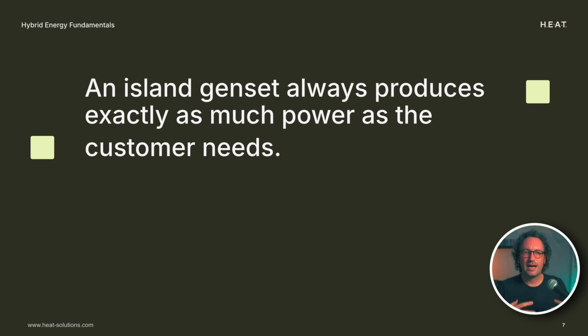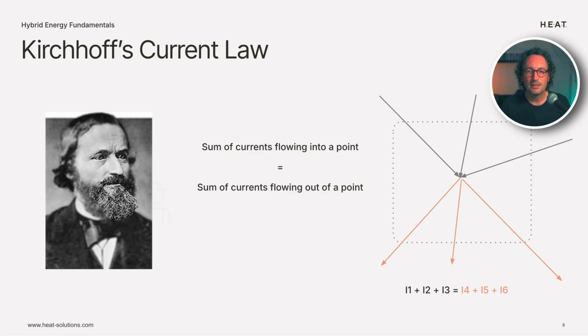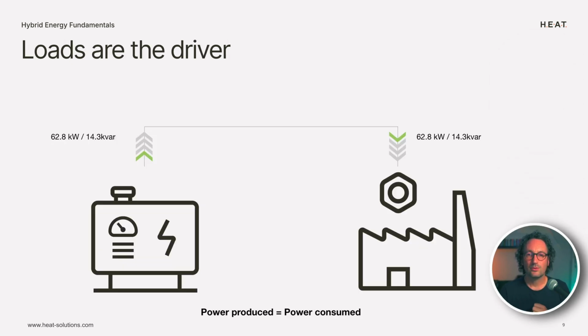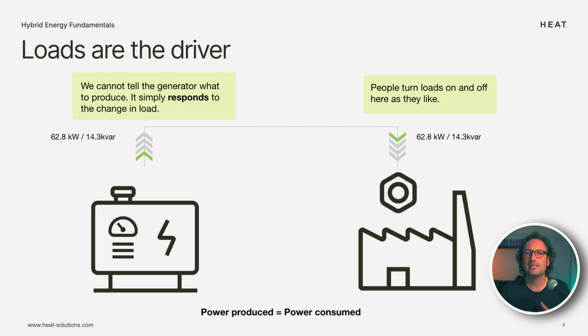Okay, so we know that an island genset is always producing exactly as much power as the customer needs. But the big question is, how does it know? And for that, I'm going to refer to Kirchhoff's current law. Kirchhoff's current law states that the sum of currents flowing into a point is always exactly equal to the sum of currents flowing out of a point. And the key thing here is that this is always true whether you like it or not. It's a physical reality of the world that we live in. Nobody's got to make it happen. It just is true all the time, no matter what. So if we take a look at our island genset again, we can see that people turn loads on and off as they like. And the genset simply responds to these changing loads through Kirchhoff's current law. And this means that load draws power out of the generator, right? The load is the active thing that's changing, and it's the driver.